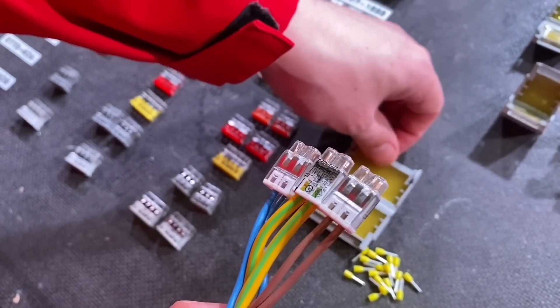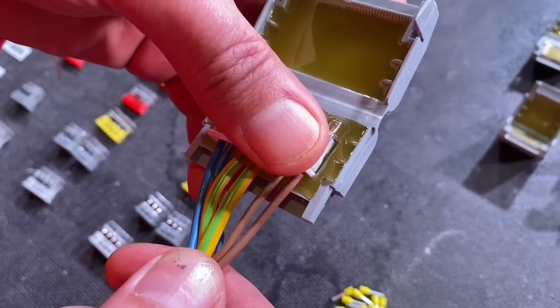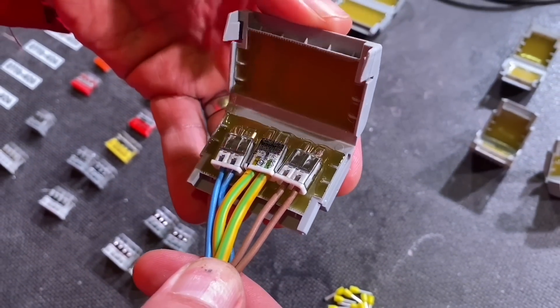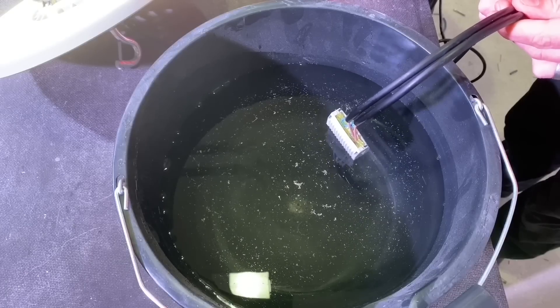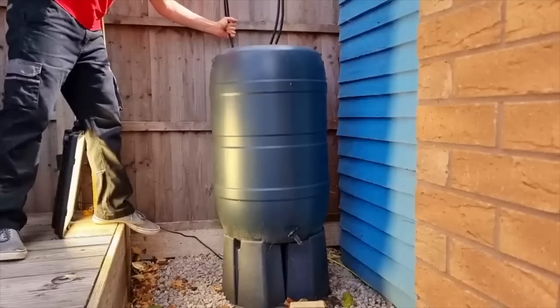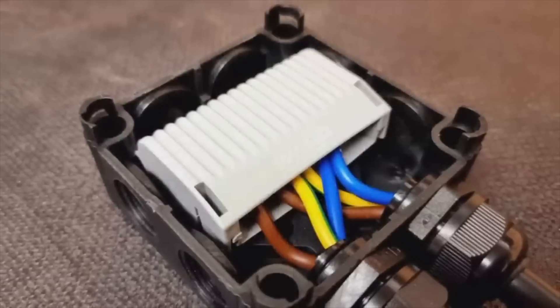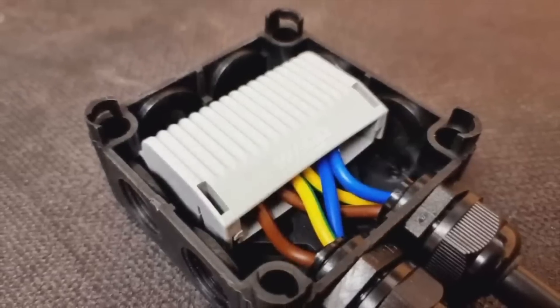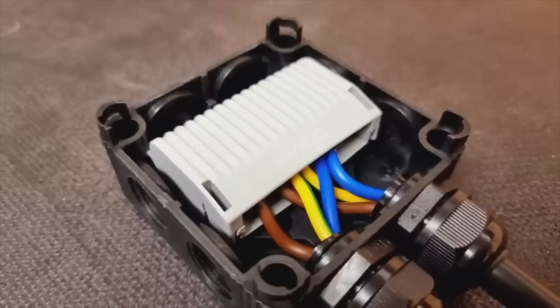This question came about when Gary and Gordon tested the Wago IPX8 range of gel boxes and showed in their video that the termination stood up to being submerged in a bucket of water. In a later video, Joe tested the boxes again to the required rating for IPX8 in one metre of water. In both videos we saw how the Wago gel box was placed inside an enclosure, and although the connections were IPX8, the full termination was not and had to be enclosed in a box for basic protection.